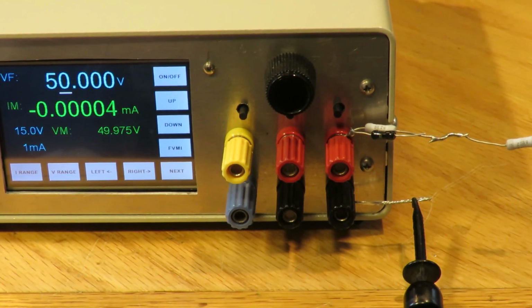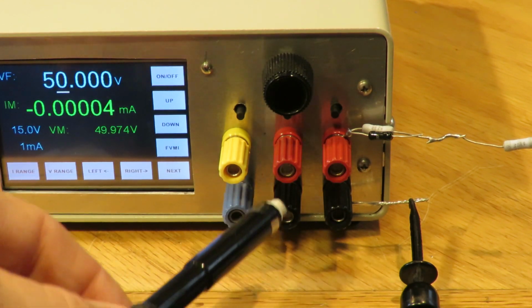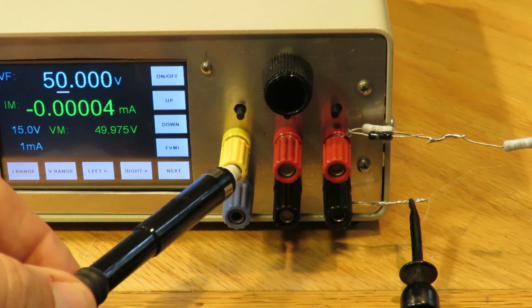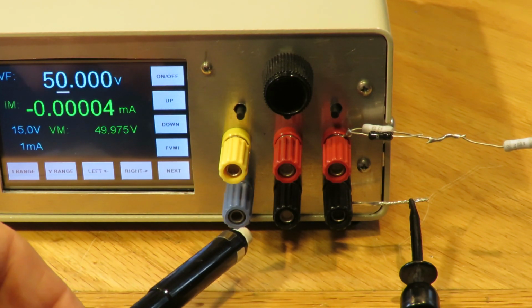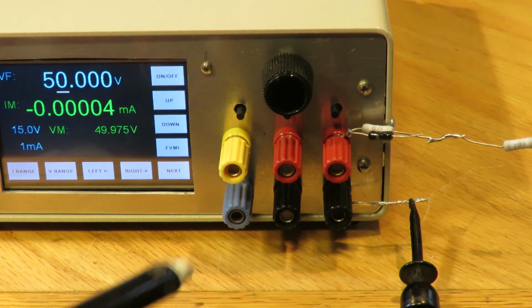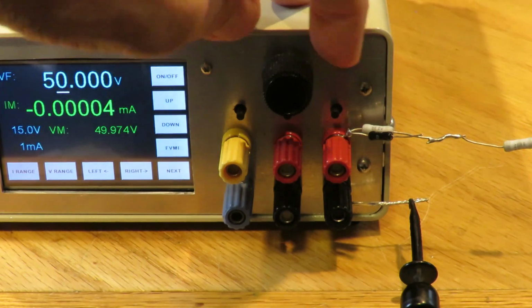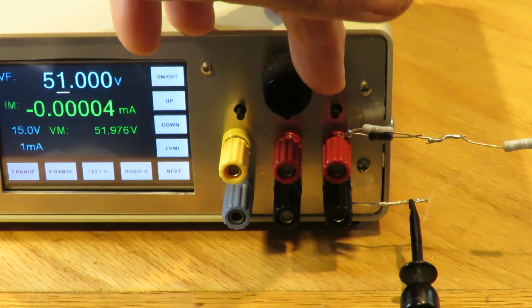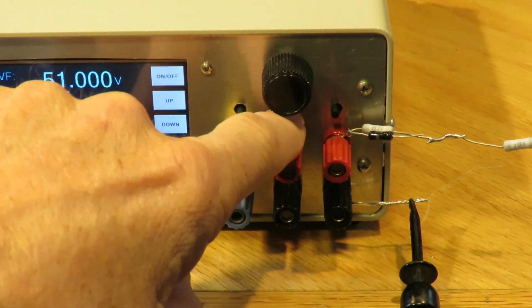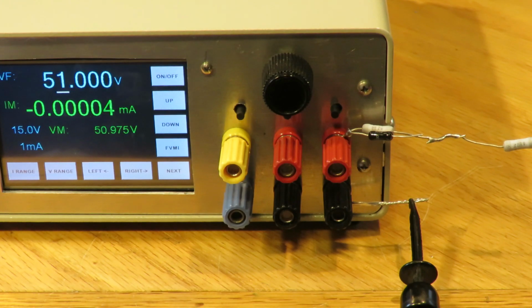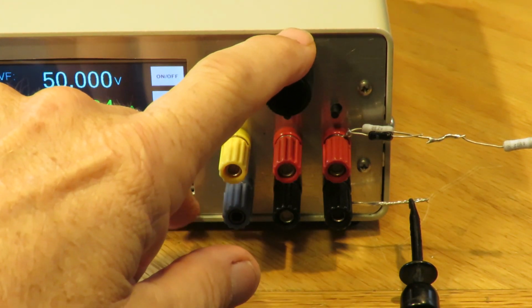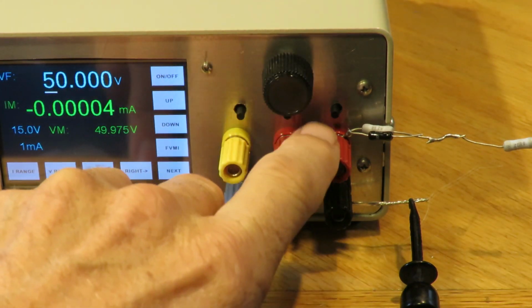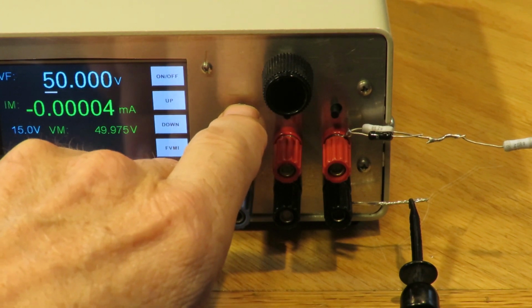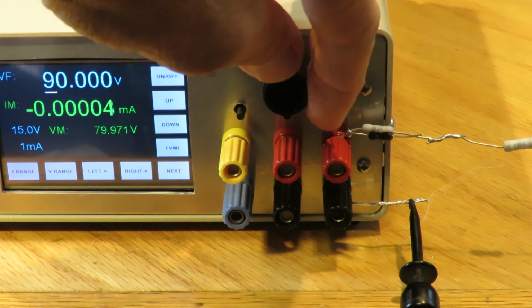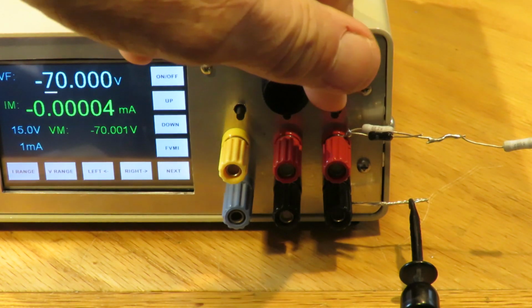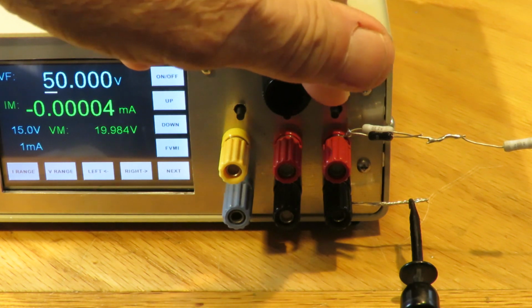The jacks on the right are the force output jacks. These are the remote sense jacks. This is the guard, and this is the ground, the chassis ground. You can see I didn't have a green jack. There's front panel controls. There's one to control the value, and there's a couple of buttons down here to control the digit selection. So right now we're at 50 volts, and you can see I can move the cursor. These control the cursor, so I can move the cursor around 50, 60, 70, 80, 90, 100 volts, and I can go up from minus 150 to plus 150 volts.